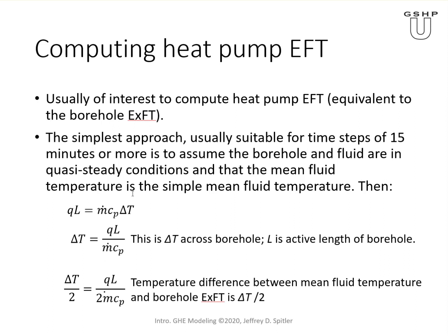We can solve this energy balance for delta T: it equals Q·L divided by ṁ·Cp, the total heat input divided by the mass flow rate times specific heat. Then delta T over 2 is the temperature difference between the simple mean fluid temperature and the borehole exiting fluid temperature, given by this expression.